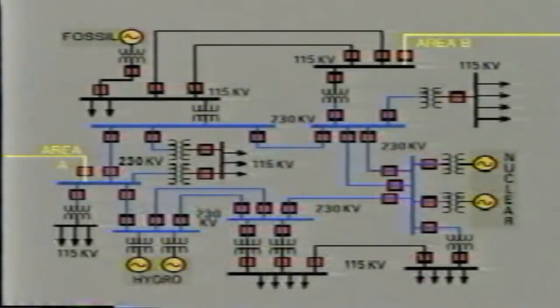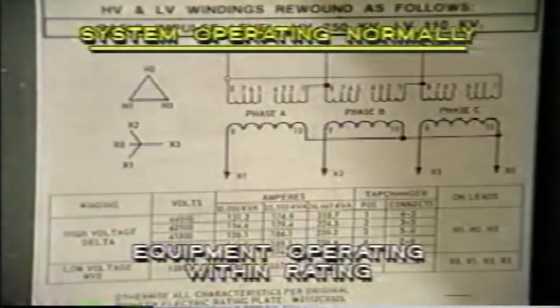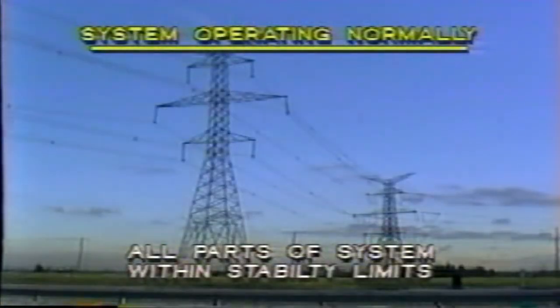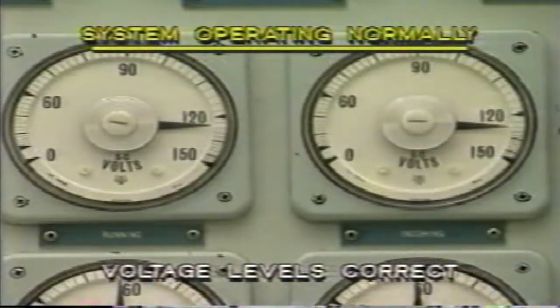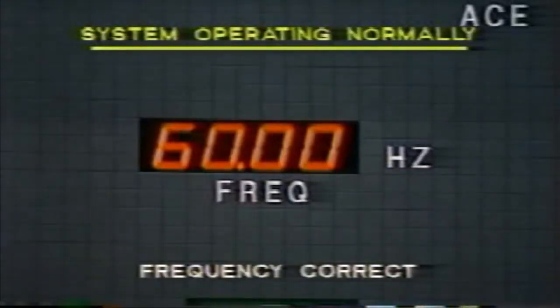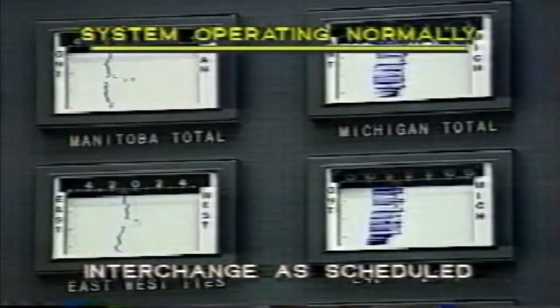When we speak of system security, we refer to its ability to withstand overloads and disturbances. The power system is considered to be operating normally when all of the equipment is operating within its specified rating, all parts of the system are working well within their stability limits, that is, the power angle is low, voltage levels are correct throughout the system, frequency is correct, and sufficient reserve generation capacity is online to accommodate load changes, and interchange between neighboring utilities is as scheduled.